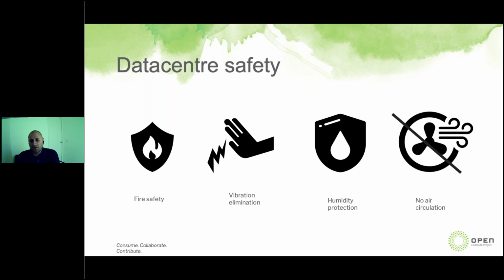The servers are located in a protective environment that prevents the spread of fire and prevents the impact of the sound shockwave of the fire extinguishing system, prevents the ingress of water into the servers, and prevents open or short circuits due to contamination. There is no air circulation that can spread fire, and air conditioners are removed from the hall, which is a potential source of fire.